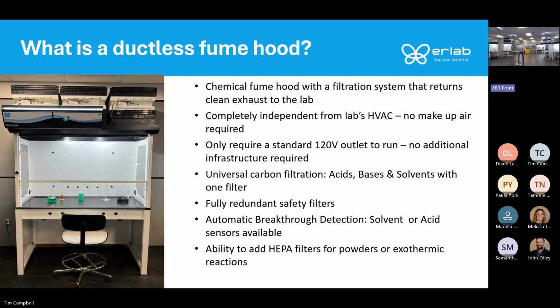That picture, it's hard to see, but there are HEPA filters on the hood that goes on first. And that's what sets us apart. We have that flexible filtration column where you can add HEPA filters if you're using powdered or having any exothermic reactions. It's actually very common today. I'd say probably about 60% of our applications now have HEPA filters on the hood.